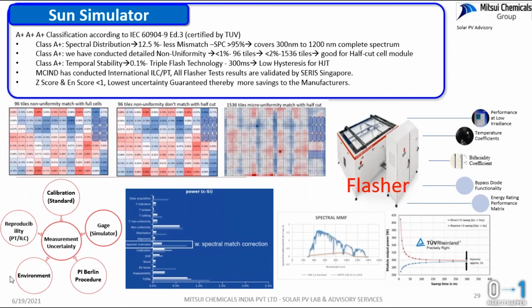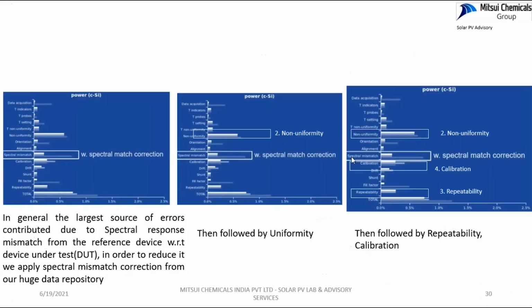I don't want to go into detail. Basically these are the non-uniformity maps for full cell and half cut cell, and we generally measure at every inch of the sun simulator, so we know the error contributing to the measurements. This slide shows the major contributors in power measurements, because power is the driving factor in the PV market: the spectral mismatch correction, which is a majorly neglected thing, non-uniformities, calibration, and repeatability of the equipment itself.